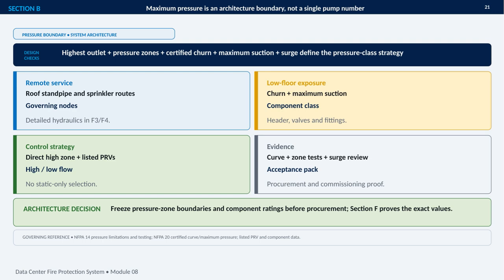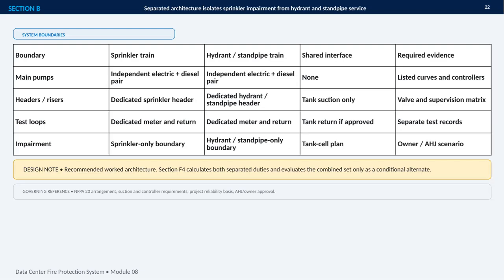the governing references. This slide defines the system boundaries for a separated fire protection architecture. The central idea is that a sprinkler impairment should not automatically disable hydrant and standpipe service, and the reverse should also be true. Each duty has its own complete train. For the sprinkler system, that means an independent electric and diesel pump pair, a dedicated header and riser arrangement, and a dedicated test meter with its own return.